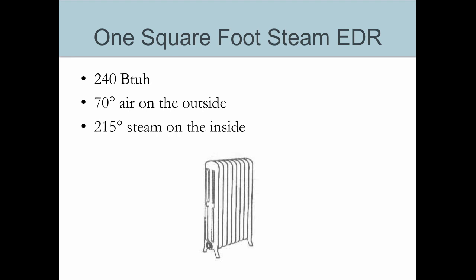They got very concerned about the safety issue in 1899 and held a meeting in Manhattan at the Murray Hill Hotel on Park Avenue — December 18th and 19th. They decided that from then on, all steam boilers should be run at 2 psi, and all hot water boilers at 180 degrees. They established that steam EDR puts out 240 BTUs per hour, while hot water with an average water temperature of 170°F only puts out 150 BTUs — a factor of 0.6. They also established the pickup factor to account for heating pipes before heating radiators. These people in two days pretty much changed the face of heating as we know it.